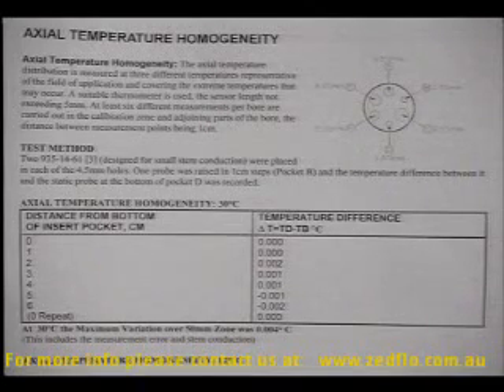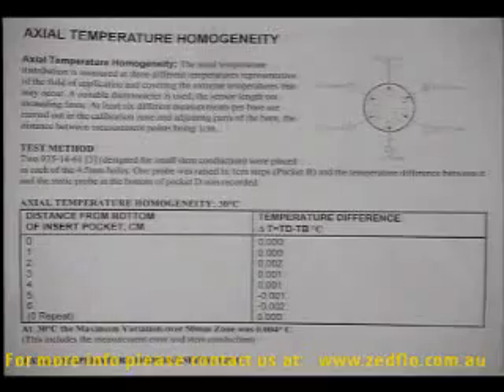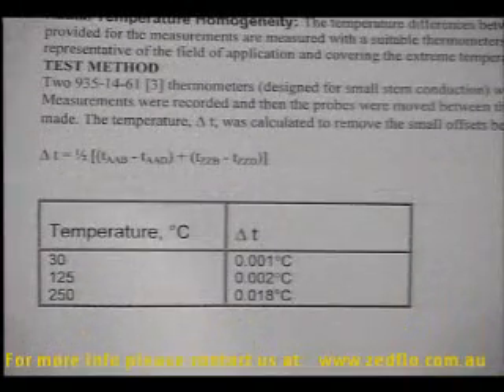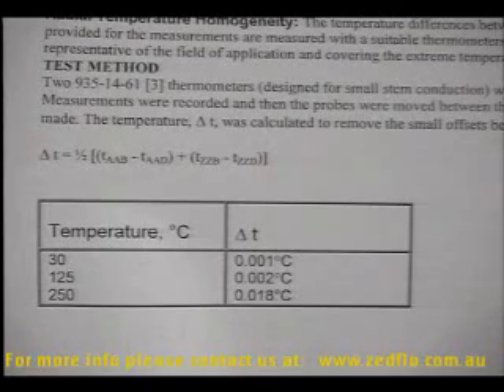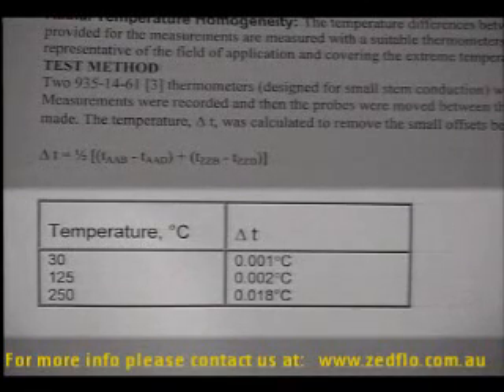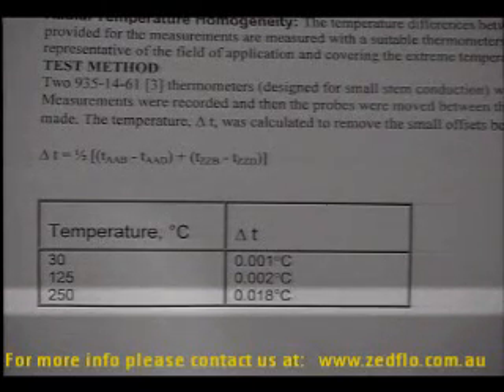This table shows how the temperature inside the metal insert changes as we take the sensor slowly out of the insert. These represent withdrawal distances. This is at the bottom, and this is 6 centimeters up from the bottom of the insert pocket. As you can see, at 30 degrees Celsius, the error in temperature is so small that it is almost negligible. Another thing we need to know about the Isocal 6 insert is the temperature variation across the block. If we put temperature sensors at the bottom of different pockets, what kind of temperature gradient can we expect? This table shows the results of tests carried out at 3 different temperatures, at 30 degrees, 125 degrees, and at 250 degrees Celsius, and the temperature gradients are less than about 20 millikelvins over the whole range.